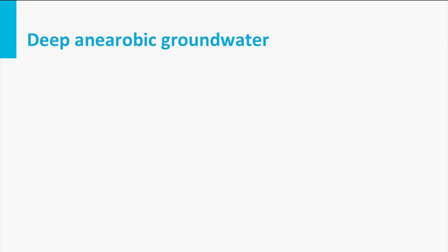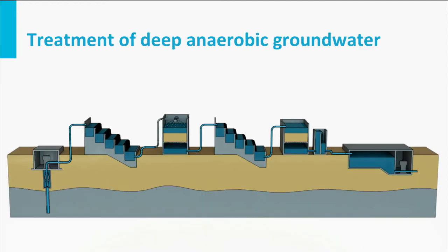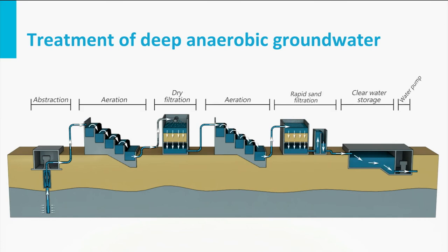The last treatment scheme is for deep anaerobic groundwater. Both oxygen and nitrate are absent in this groundwater, and organic material is broken down with sulphate as an oxidant. In deep anaerobic groundwater, iron, manganese, and especially ammonium are present in high concentrations, in addition to hydrogen sulphide and methane. For the removal of ammonium, a lot of oxygen is required — even more than can be dissolved in the water during aeration, in other words more than the saturation concentration. To prevent anaerobic conditions in the sand filter, double submerged filtration or dry filtration can be applied, followed by regular submerged filtration in case of high ammonium concentrations.